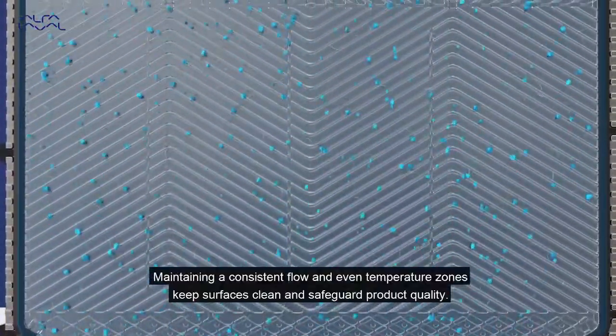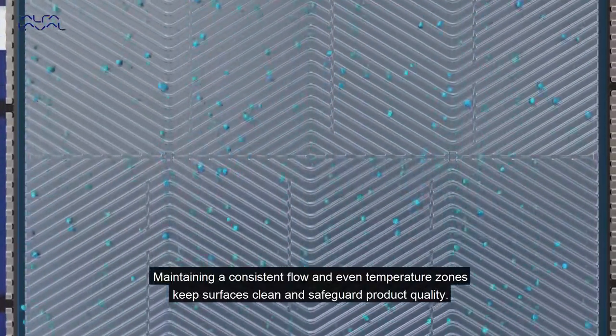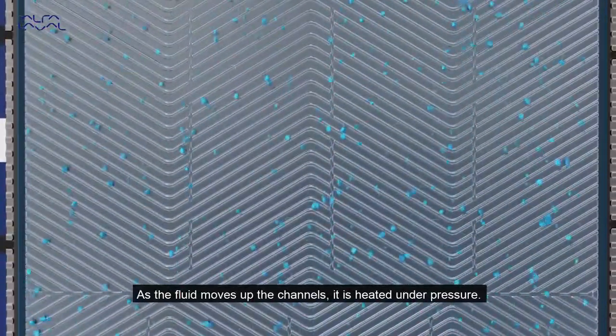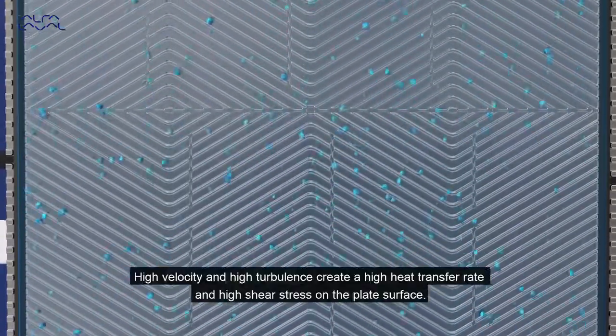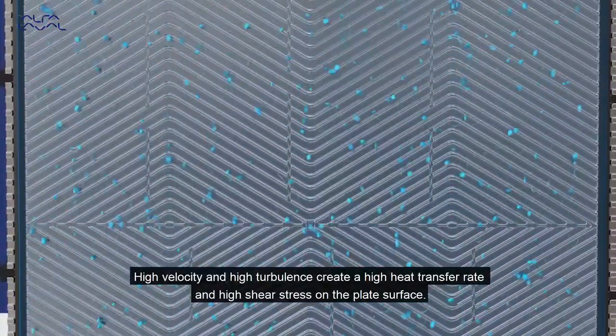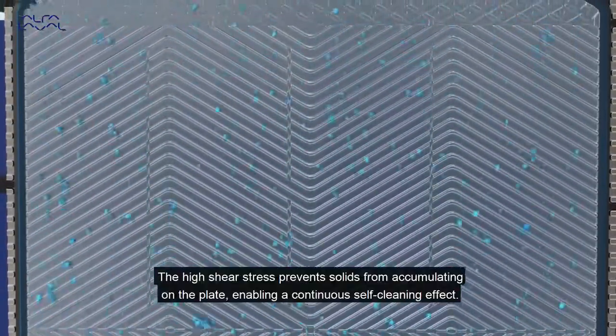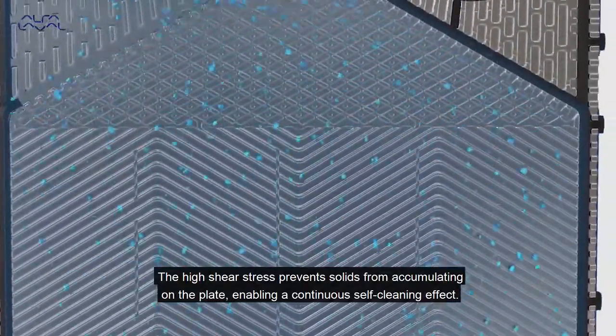Maintaining a consistent flow and even temperature zones keeps surfaces clean and safeguards product quality. As the fluid moves up the channels, it is heated under pressure. High velocity and high turbulence create a high heat transfer rate and high shear stress on the plate surface. The high shear stress prevents solids from accumulating on the plate, enabling a continuous self-cleaning effect.